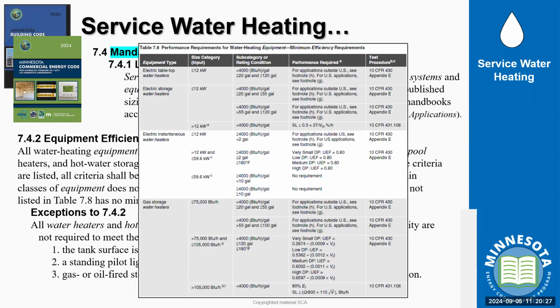However, now we have to calculate into that the line sizes, the minimum sizing of our gas lines, because we went from a 45,000 BTU water heater to a 190,000 BTU instant hot water unit. It sounds like a reasonable solution. We're getting rid of a large piece of equipment, putting in a smaller piece of equipment, but really we're dynamically changing the expectations on the overall system.